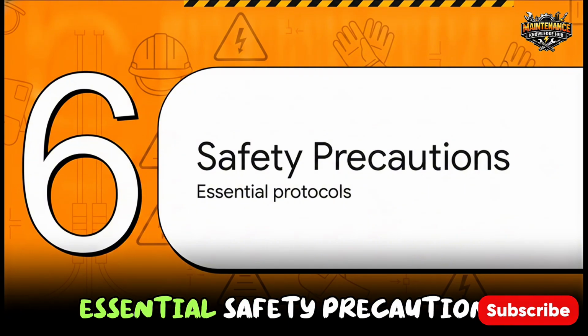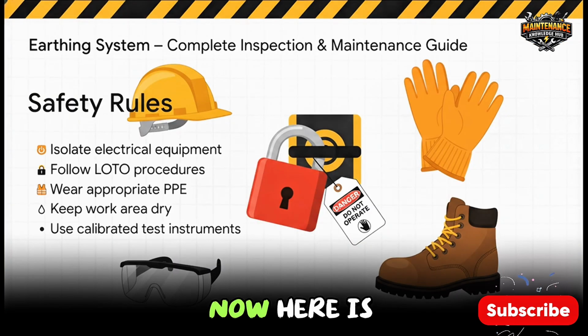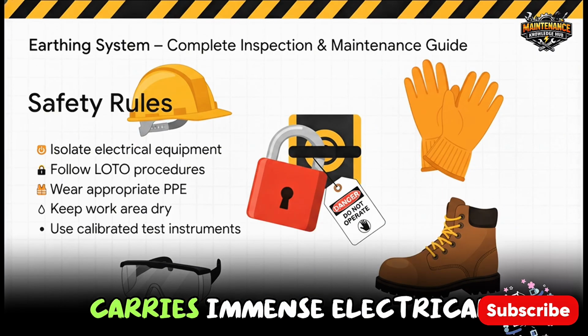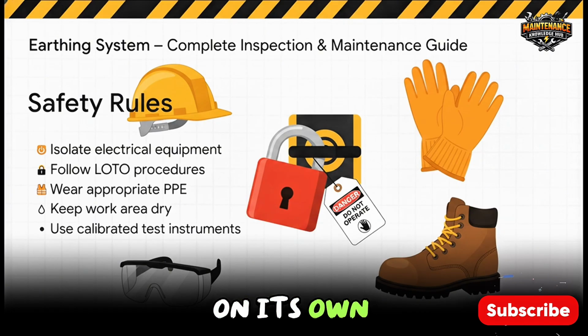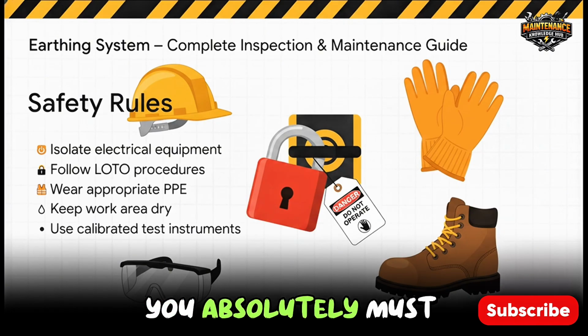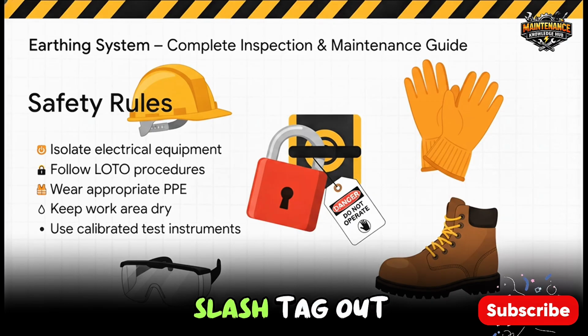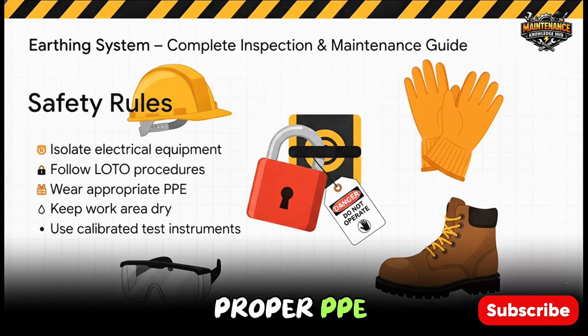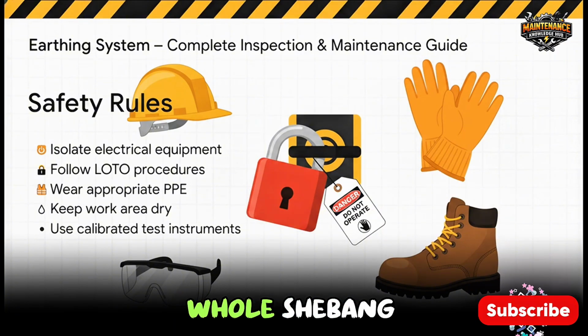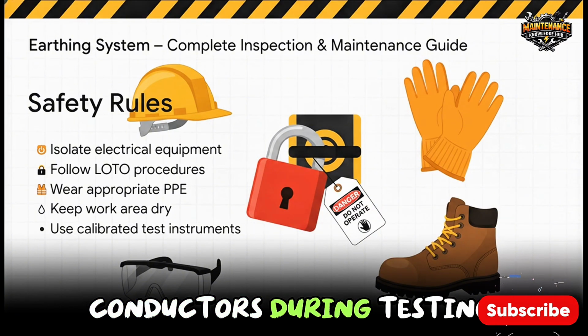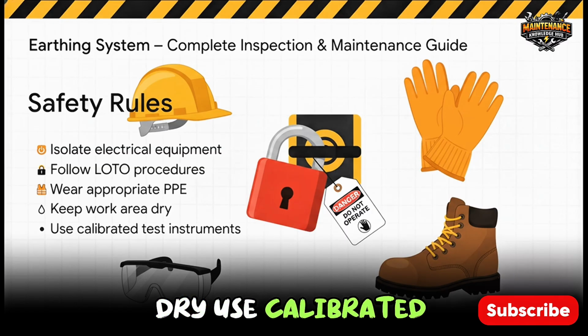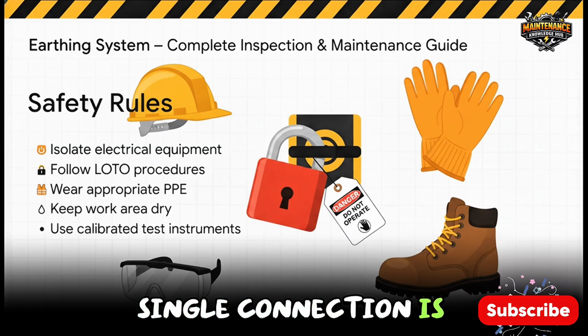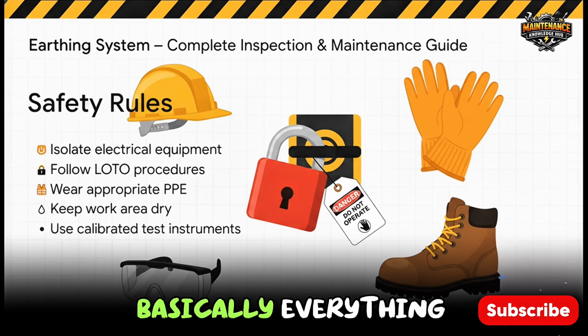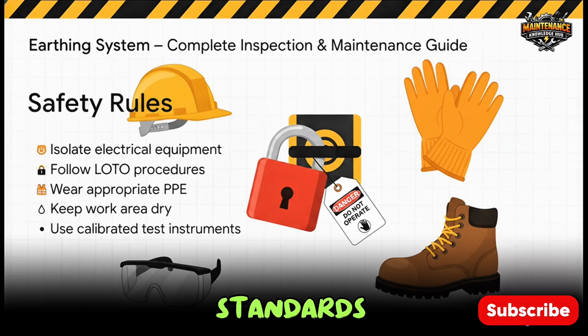Finally, Section 6, Essential Safety Precautions. Now, here is the ultimate irony of all this. Testing a life-saving safety system carries immense electrical risk on its own. Never cut corners here. You absolutely must isolate equipment and follow rigorous lockout/tagout procedures. Wear the proper PPE. We're talking insulated gloves, safety shoes, the whole shebang. Never touch exposed conductors during testing. Keep your area dry, use calibrated instruments, and ensure every single connection is flawlessly restored before you re-energize. Basically, everything you do should strictly follow applicable standards like IEC 60364 and IEEE 80.